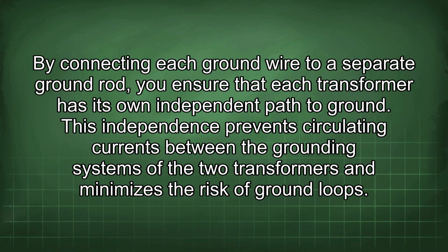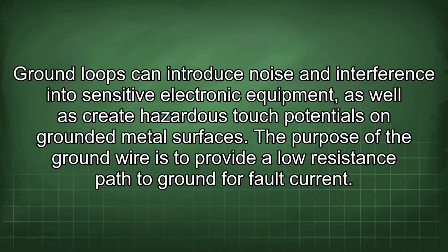By connecting each ground wire to a separate ground rod, you ensure that each transformer has its own independent path to ground. This independence prevents circulating currents between the grounding systems of the two transformers and minimizes the risk of ground loops. Ground loops can introduce noise and interference into sensitive electronic equipment, as well as create hazardous touch potentials on grounded metal surfaces.